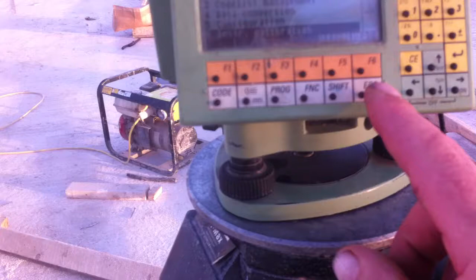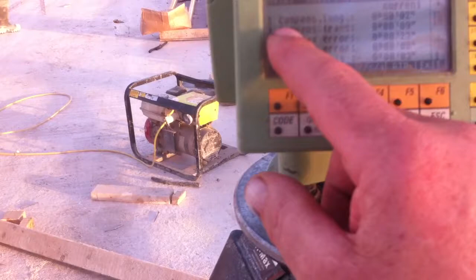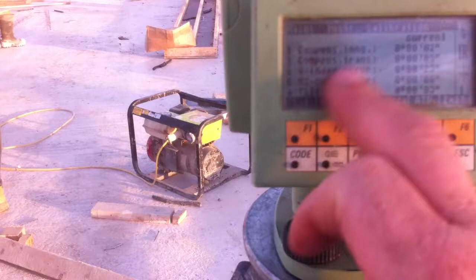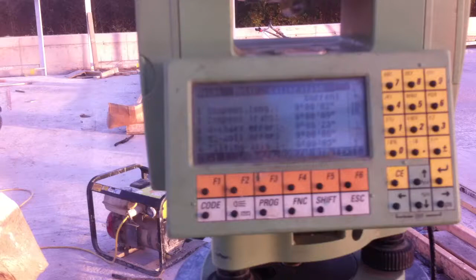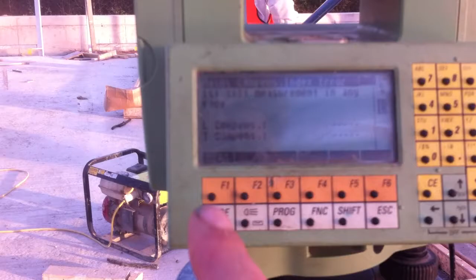Okay, so this is this machine doing it. The first thing we're going to do is go to instrument calibration, and we're going to check the spirit level bubbles on it. The last time I checked it in the office, it was 2 seconds and 9 seconds correction in the compensator, longitudinal and transversal. So what I'm going to do now is a quick check on it. Alright, so here we go.